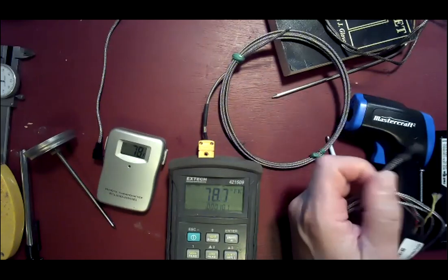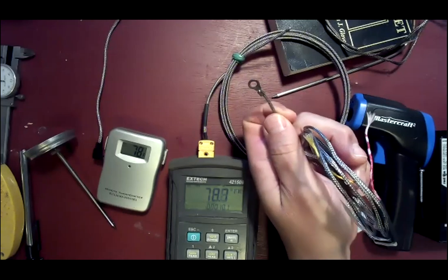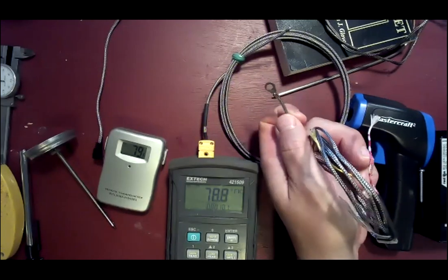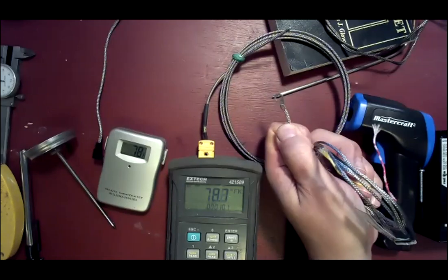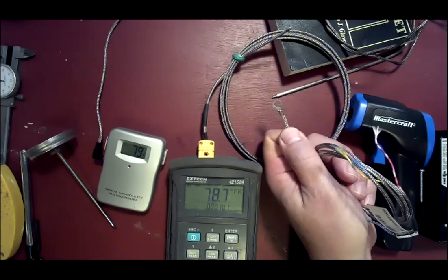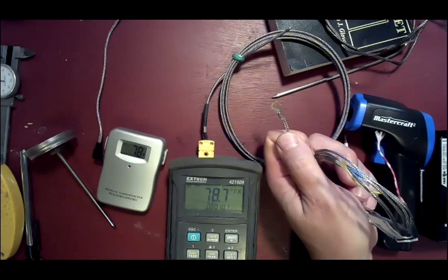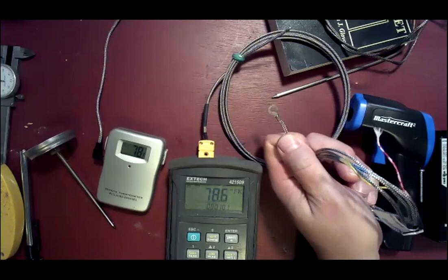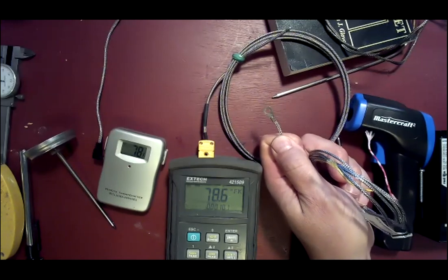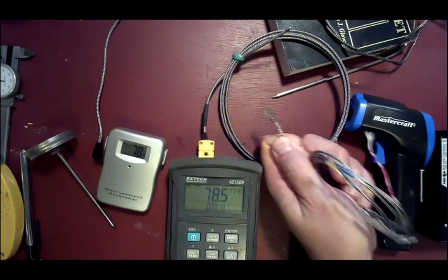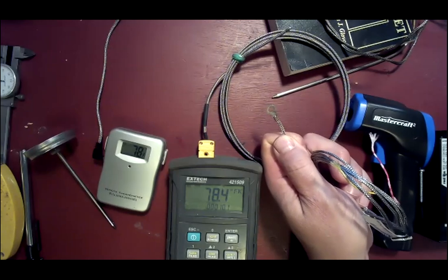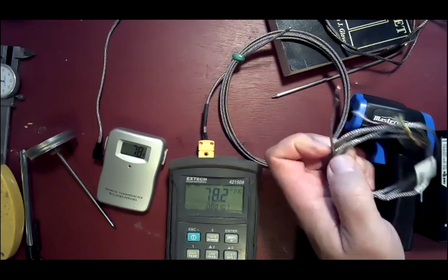On the bulb system, I use a spring-loaded device. But if you're measuring the temperature of, say, a duct, you would use a little probe that's designed like this. This is actually a temperature probe with a little eye at the end of it that I can screw down to get a really accurate surface measurement. Not nearly as accurate as getting inside the chamber, but better than just pushing up against something. So surface measurement is actually kind of challenging.